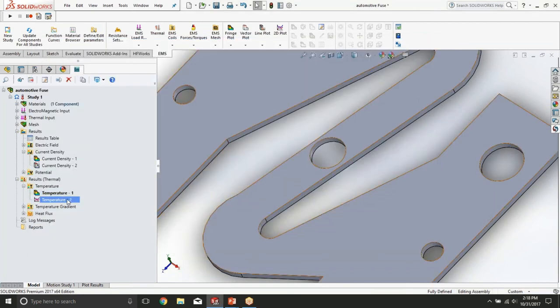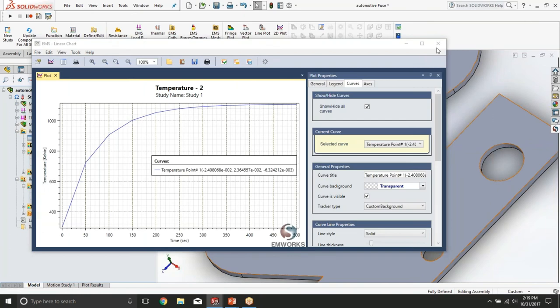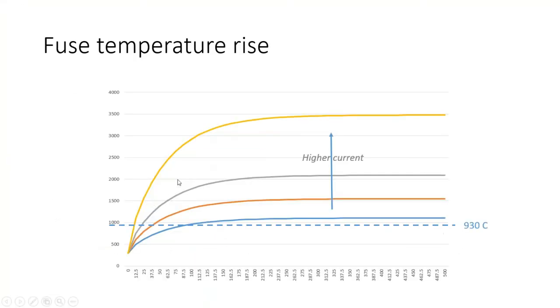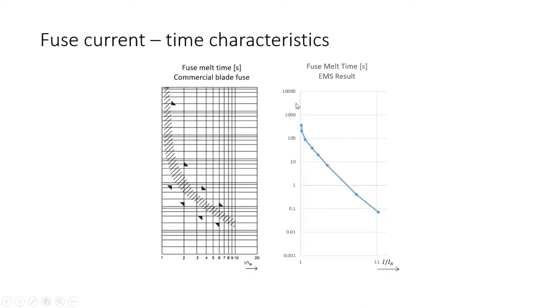If we plot a few of these plots for different currents, we can see how much time it actually takes for each current to melt the fuse. The higher the current, the less time it will take to reach this 930 degrees point, and the less time it will take to melt the fuse. This will allow us to plot the fuse current time characteristics.